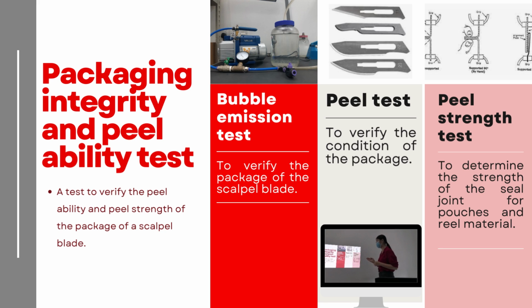For the bubble emission test, the purpose is to verify the package of the scalpel blade. And then the next is the peel test. The peel test is to verify the condition of the package. So we will observe the smoothness when we open the package of the scalpel plate. If there is any breakage or leakage happening when we're doing the bubble emission test, the peel test will be considered failed.